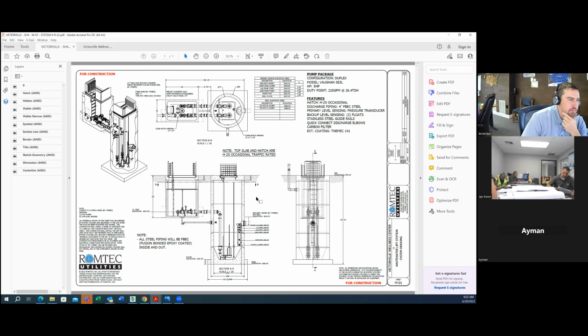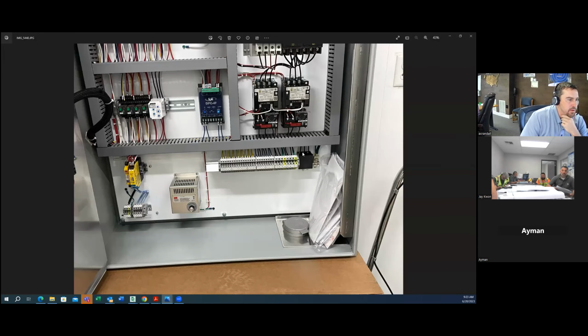Sure. At the bottom of the control panel, we also need to make a conduit coming up for the sensors. On the left side, one is for power and one is for the sensor, so we make penetrations. Two of the left side's penetrations are the 1-inch conduit for level sensing. We'll have 2 floats and the pressure transducer in it, and then 2 conduits over here for the pump cables.